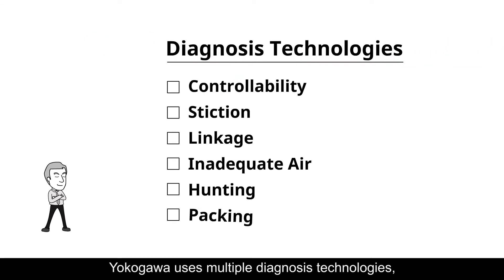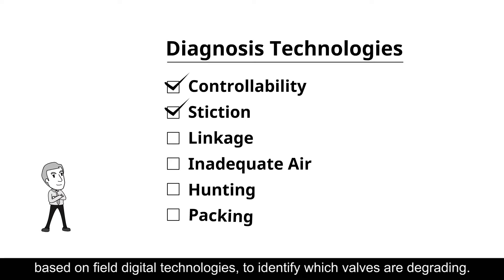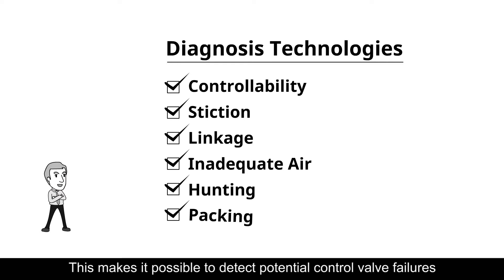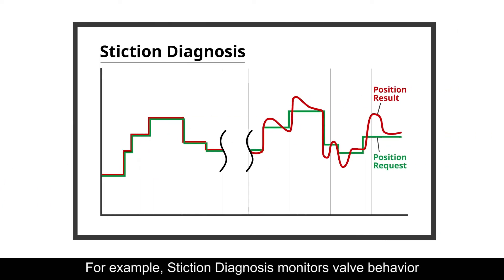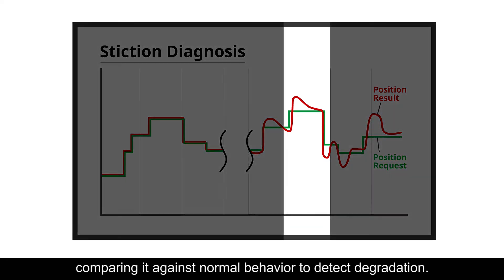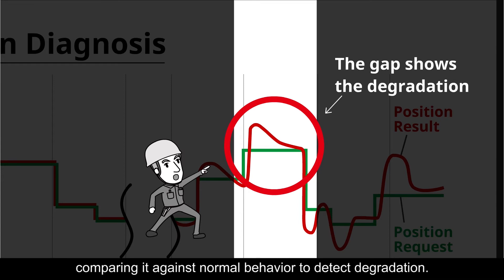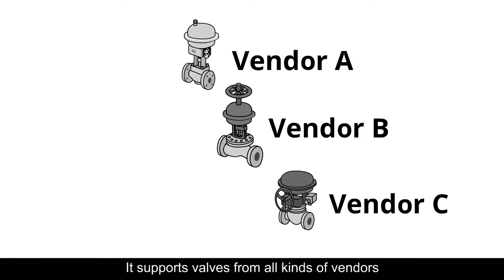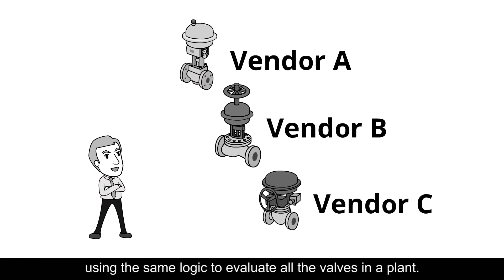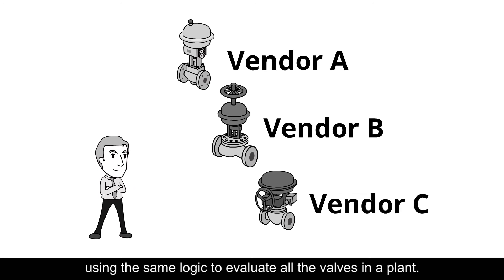Yokogawa uses multiple diagnosis technologies based on field digital technologies to identify which valves are degrading. This makes it possible to detect potential control valve failures before they happen. For example, stiction diagnosis monitors valve behavior, comparing it against normal behavior to detect degradation. It supports valves from all kinds of vendors, using the same logic to evaluate all the valves in a plant.